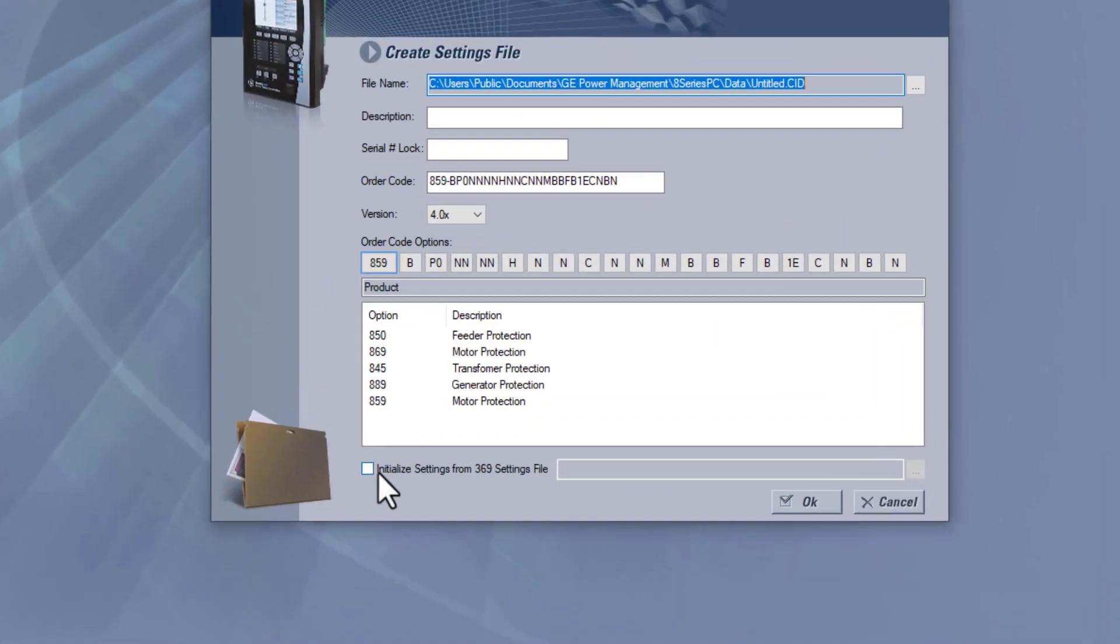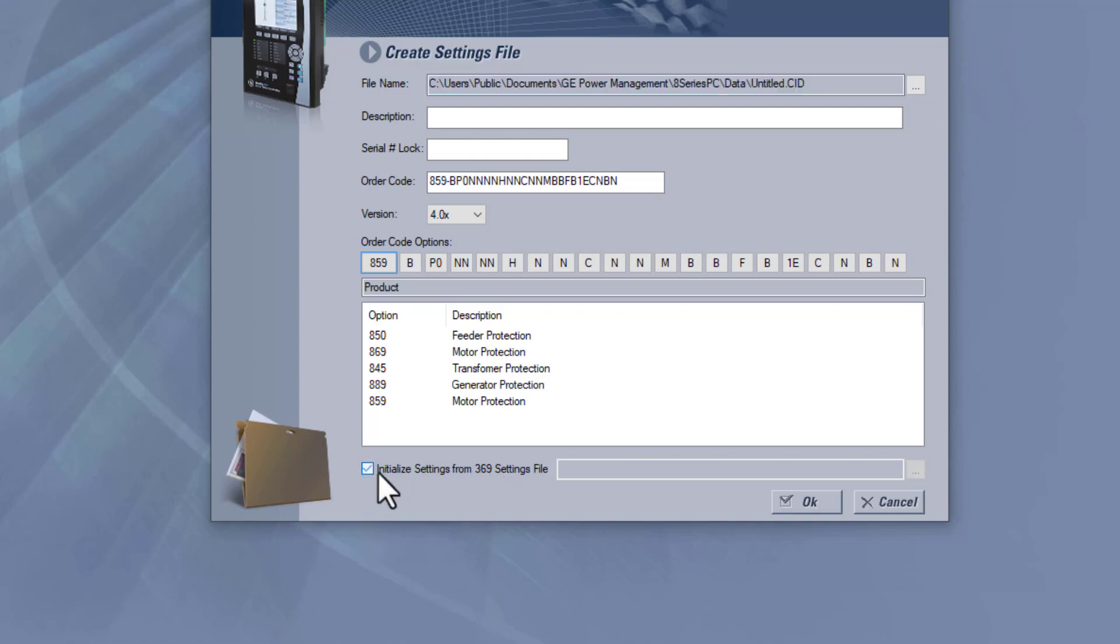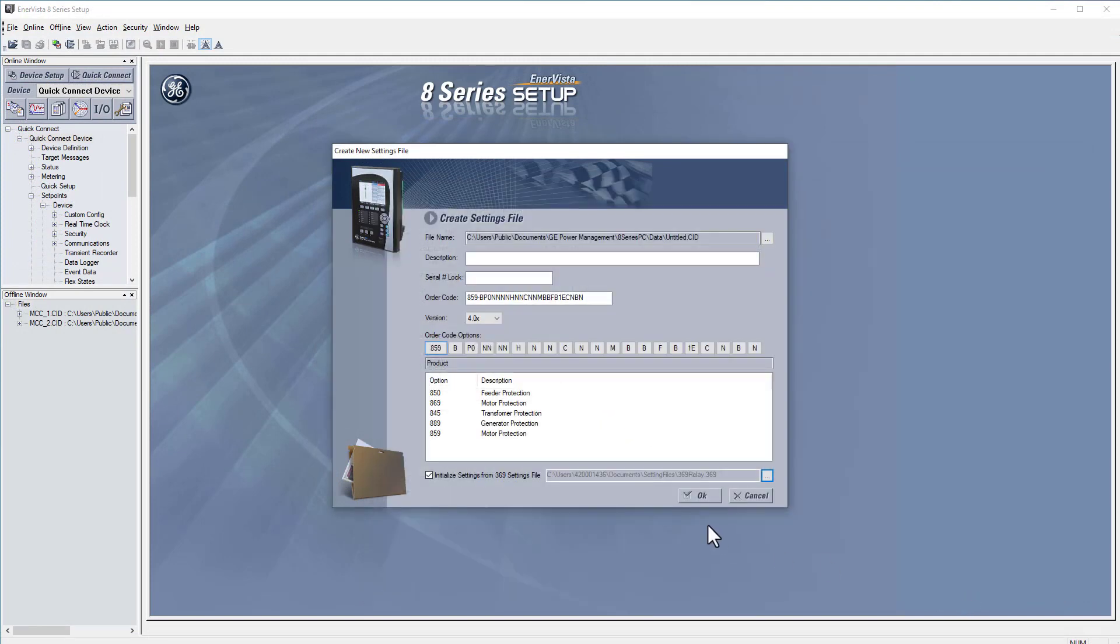At the bottom there's a checkbox to initialize setting file from 369 setting file. Check this box and click the three dots to select the 369 relay dot 369 setting file, then click open and click OK.